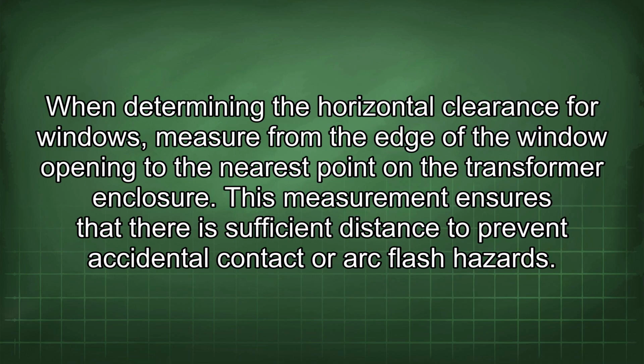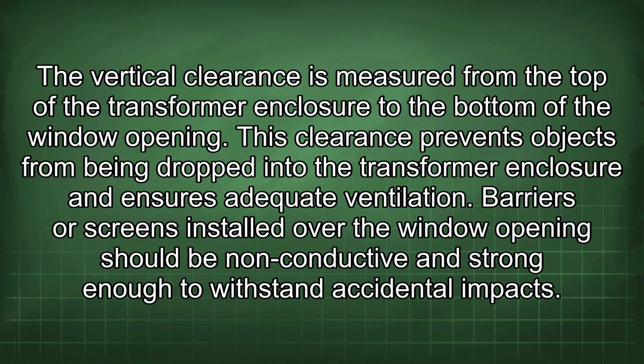When determining the horizontal clearance for windows, measure from the edge of the window opening to the nearest point on the transformer enclosure. This measurement ensures that there is sufficient distance to prevent accidental contact or arc flash hazards. The vertical clearance is measured from the top of the transformer enclosure to the bottom of the window opening. This clearance prevents objects from being dropped into the transformer enclosure and ensures adequate ventilation.